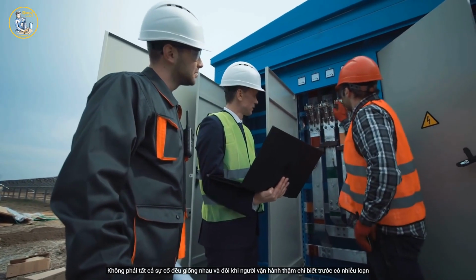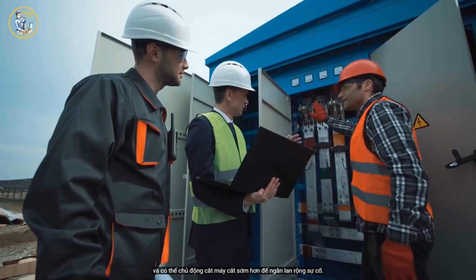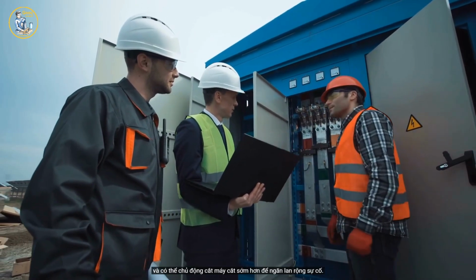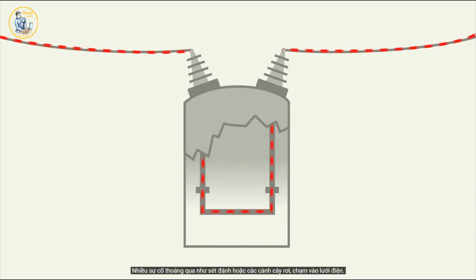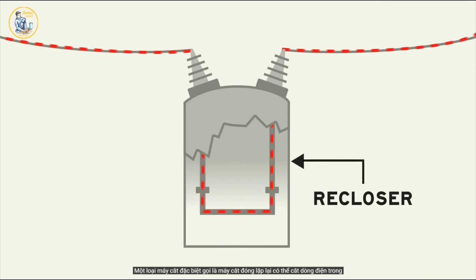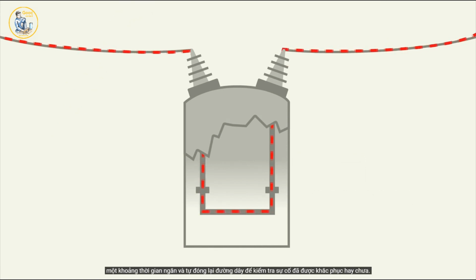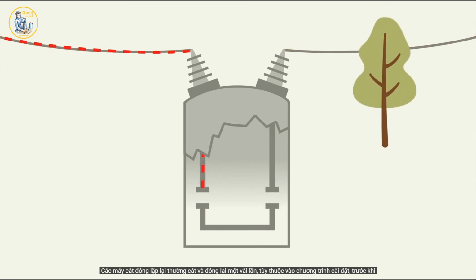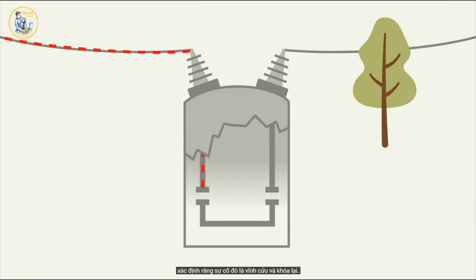Not every fault is the same, and sometimes operators even know about a disturbance ahead of time and can trigger breakers early to prevent cascading failures. Many faults are temporary, like lightning strikes or swaying tree branches. A special kind of circuit breaker, called a recloser, can interrupt current for a short period of time and re-energize the line to test if the fault has cleared. Reclosers usually trip and reclose a few times depending on their programming before deciding that a fault is permanent and locking out.